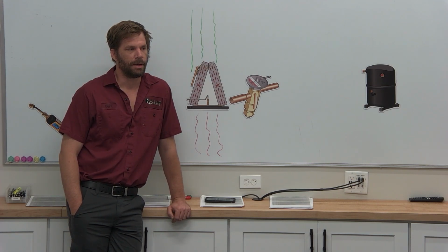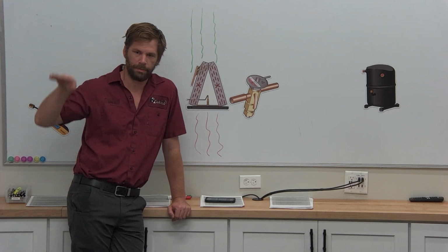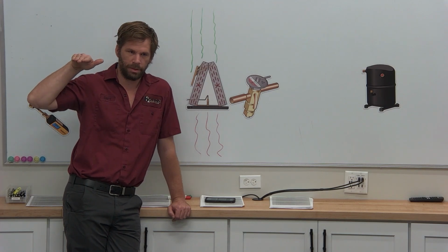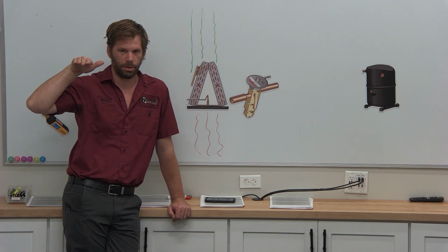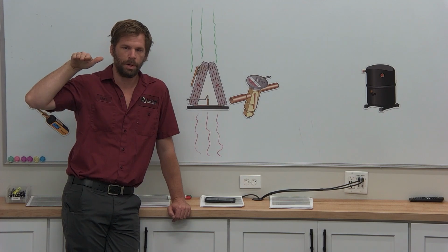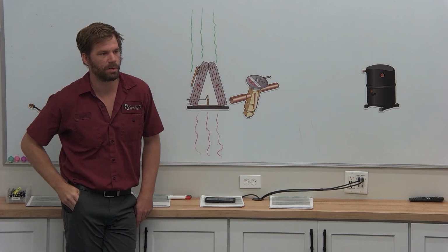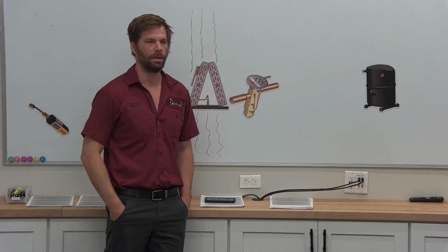And then understanding if you're getting called out because the house is not reaching temperature point. If you lower the blower speed, is the house going to reach temperature point any better? No. It'll focus more on dehumidification, maybe be slightly comfortable, but you might even see a little bit worse performance on hitting your temperature point.